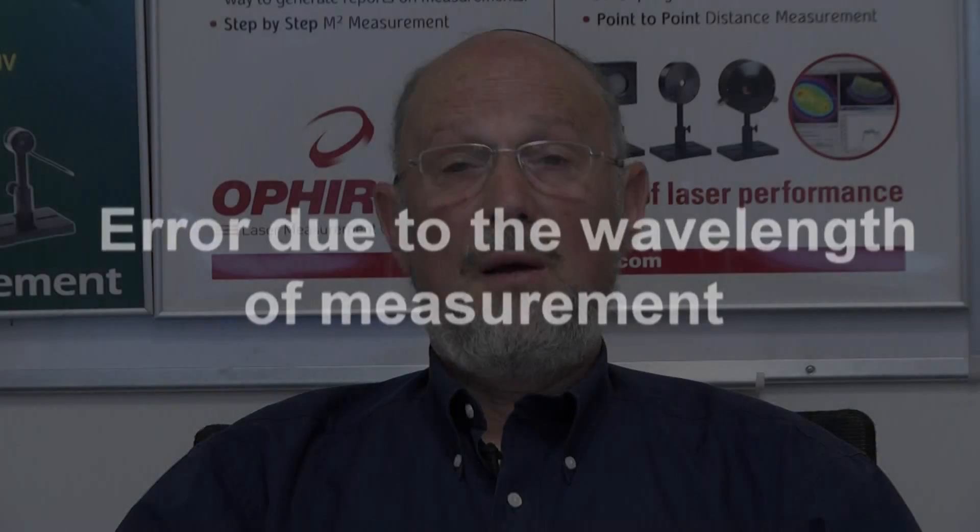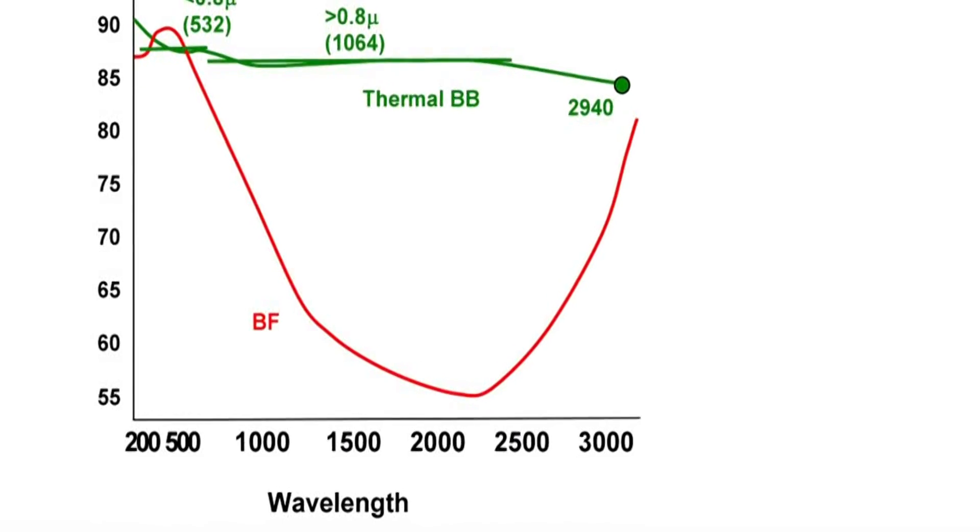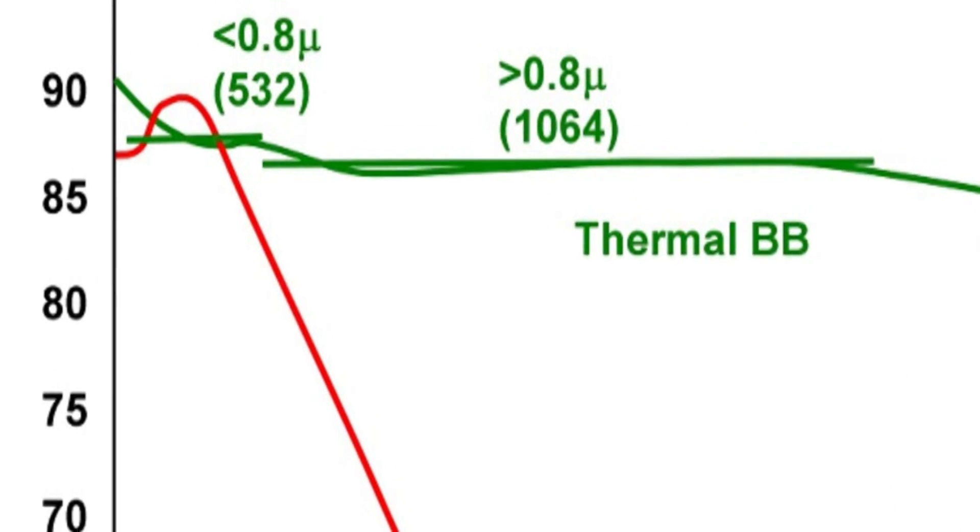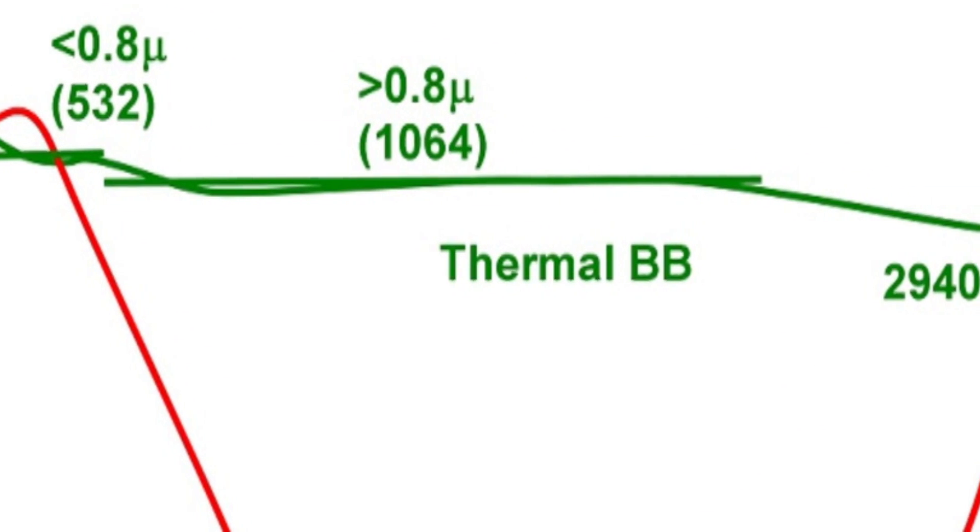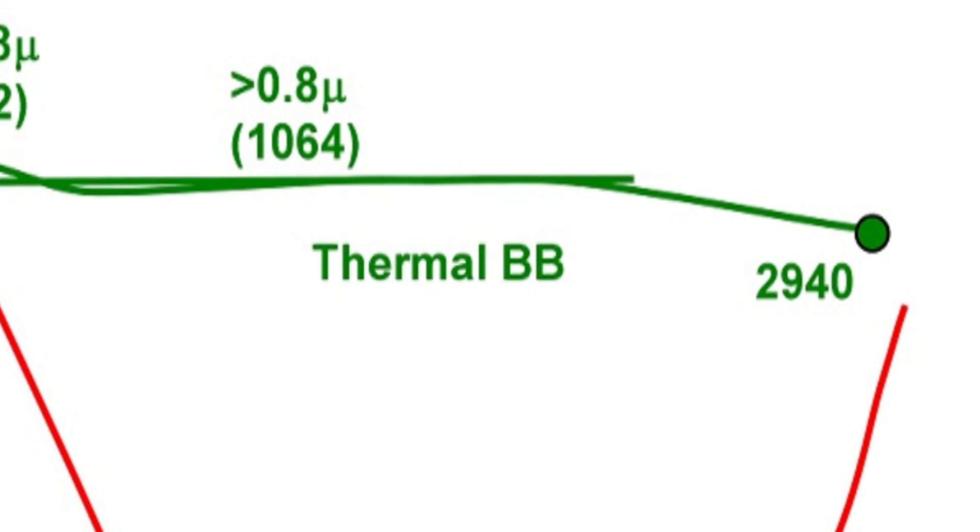Now there's another source of error we have to take into account for all of our sensors and that is error due to the wavelength of measurement. Ophir sensors absorb different amounts at different wavelengths. If we look at this graph here, we have two types of absorbers on our sensors. We have absorbers such as the green graph here that are flat with wavelength and change very little at different wavelengths. And we have absorbers that change a lot with different wavelengths such as this BF curve here with the red curve.